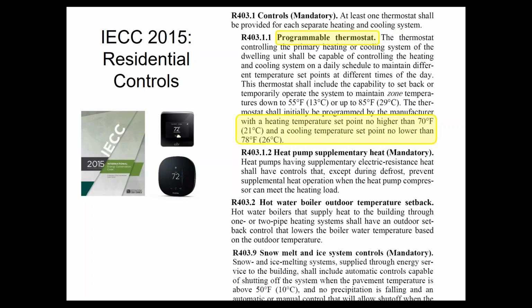You got to have a programmable thermostat. That's been in the code for a very long time. That's nothing new at all. It's got to be a programmable thermostat with schedules. Interestingly, they require the thermostat to start out with initial set points of 70 or lower for heat and 78 or higher for cooling. I don't know why they've codified that, because the building owner is going to do whatever they want later anyway. But that's technically what you got to start out with.